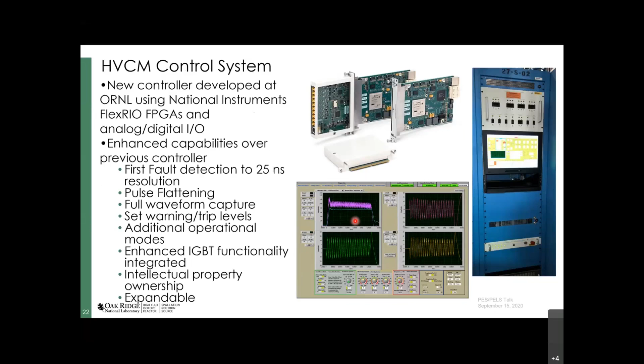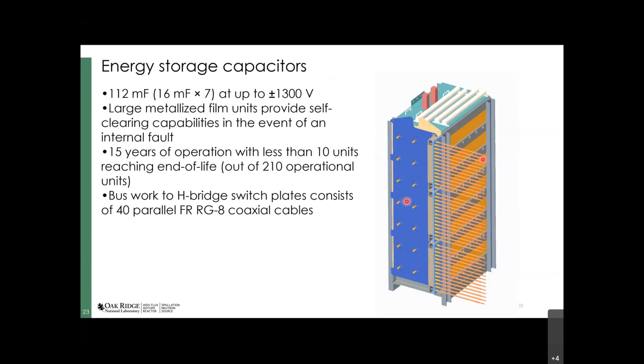These are the energy storage capacitors I mentioned earlier. They operate at plus or minus 1300 volts, and we've had really good luck with them. They're metallized film capacitors, so they fail gradually and gracefully. We go in about every 3 years to do preventative maintenance and check if they've reached end of life. With all the operational hours, we've only had to replace about 10 units, which is pretty good. To bus the power over to the H bridges, we use these parallel RG8 cables.